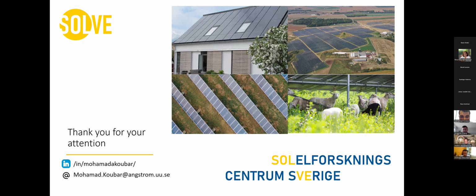FCRN is a combined service, so it's for both up and down. So if you bid in FCRN, you are obliged to operate on up and down. So it's a symmetrical service. And also there's a possibility to combine it with FCRD up and down, but you have to obey the technical requirements, which you can find, I think, on the website of Svenska Kraftnät, and you can see how much capacity you have. They have an application. You can see how much you can operate on FCRN alone, and if you want to combine it with FCRD up or FCRD down, you can find all this detail. And if you have any questions, please feel free to send an email and I can send you the links and give you other information.